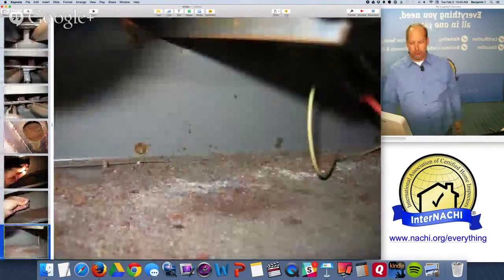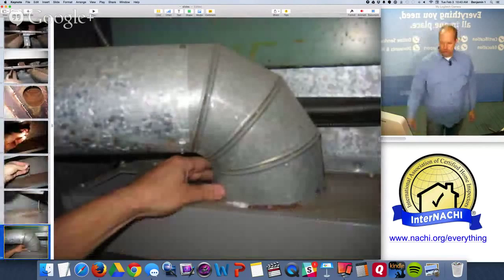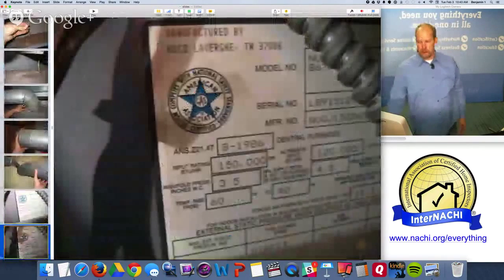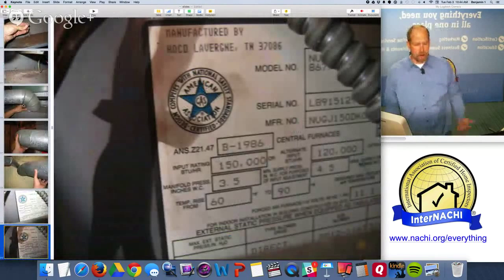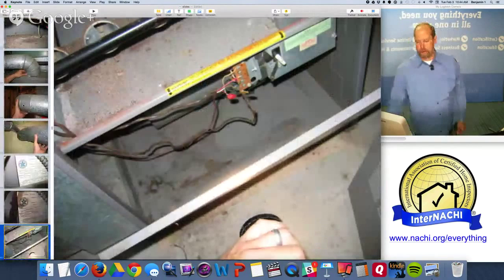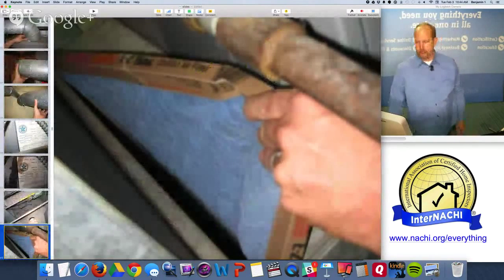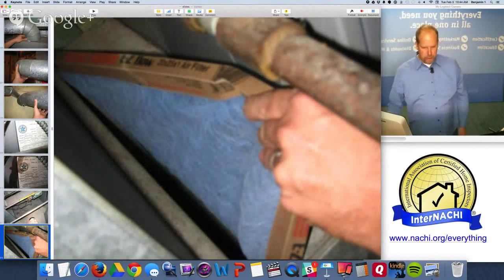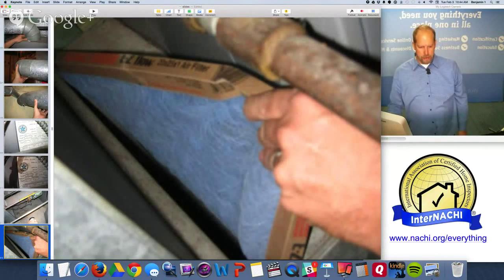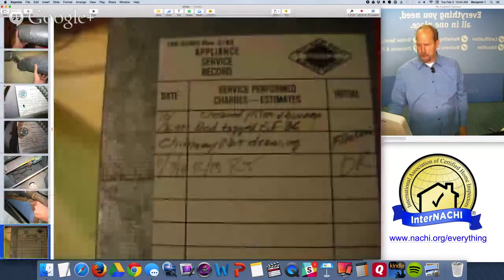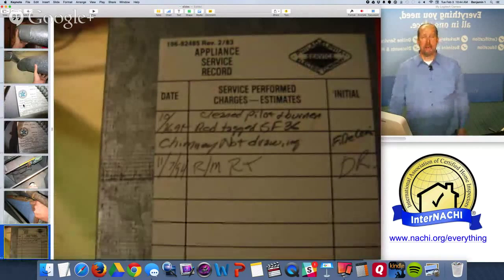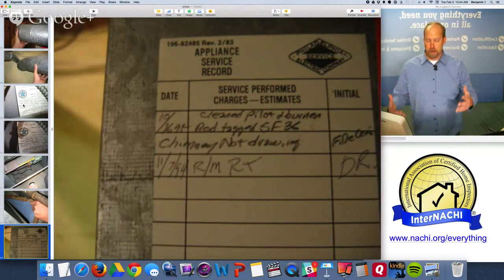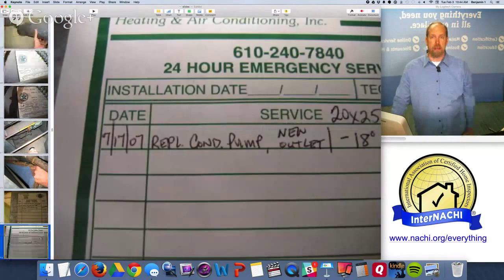The rust and corrosion going through the heat exchanger and dropping onto the bottom of the natural draft hood - before going up into the chimney stack - is an anomaly that needs to be corrected and inspected further by an HVAC professional. From the model and serial number, this unit was from 1986 - a low efficiency heating system at about 65% efficiency, essentially wasting one-third of energy up the chimney stack. The disposable air filter is being sucked into the blower fan - it hasn't been serviced or cleaned. I take a picture of the service tag and tell my client who was there last. If it hasn't been serviced within the most recent year, I recommend cleaning and servicing by a professional.